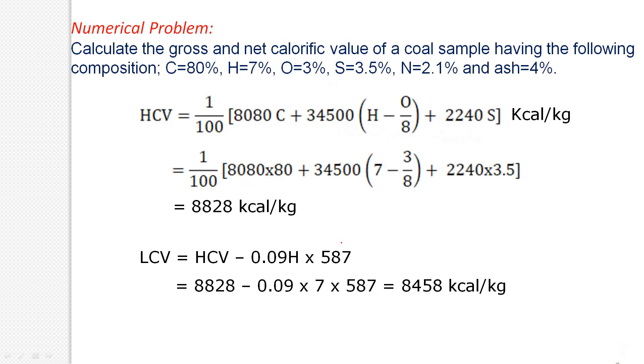Let me do one numerical problem using Dulong's formula. Calculate the gross and net calorific value of a coal sample with the following composition: Carbon 80%, Hydrogen 7%, Oxygen 3%, Sulfur 3.5%, Nitrogen 2.1%, and Ash 4%. Here, carbon, hydrogen, oxygen, and sulfur are present in the formula. Nitrogen and ash are not mentioned in the formula as they are non-combustible substances — they don't contribute any calorific value, so we need not calculate calorific value for them.